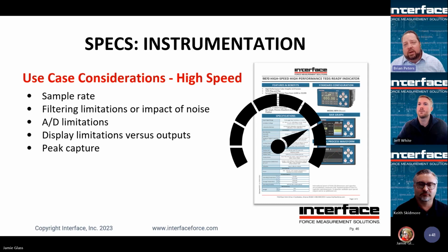So let's consider a use case of high speed. Let's say you're going to have a relatively high speed test. You want to be able to make sure that you get all the data you're looking for. Well, obviously, you're going to want to zoom in on sample rate. You're going to want to look at the filtering limitations. Sometimes you'll need to either filter noise out or not. If you do filter noise, how does that impact your ability to capture peak dynamic events? What are the A to D limitations? I mentioned that there's internal specifications, right? So what is the device capable of in terms of converting the analog signal to digital? Digital meaning the display, or digital maybe the output. Pay close attention to that. What's the speed of that? And then if you're relying on the display, what are the limitations of the ability to refresh or to keep up, right?